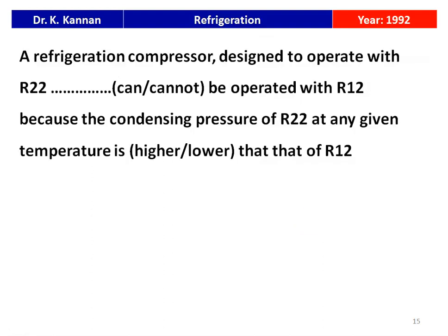The next question from the 1992 question paper: a refrigeration compressor designed to operate with R-22 — can or cannot it be operated with R-12? The correct answer is: it cannot be used. When a refrigeration compressor is designed for R-22, it should not be operated with R-12, because the condensing pressure of R-22 at any given temperature is higher than that of R-12.